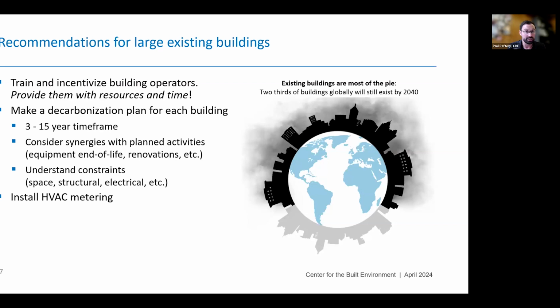Once you have that understanding, or as part of getting it, it's absolutely critical to install HVAC metering. Most buildings have very little metering, if any, other than what the utility meter shows. If you don't even know what the heating loads are in your building, it's very difficult to accurately size replacement equipment and consider alternatives like partial electrification and the full set of emissions reductions that might be feasible.